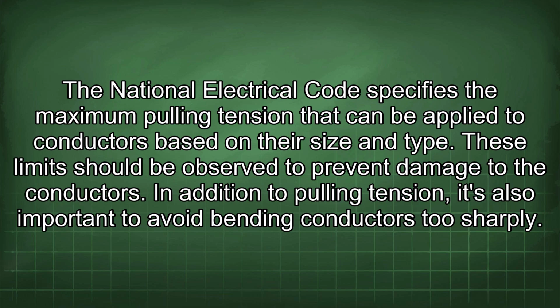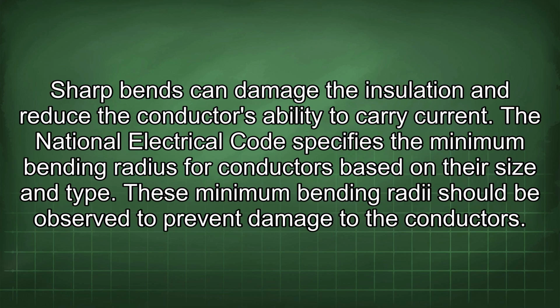In addition to pulling tension, it's also important to avoid bending conductors too sharply. Sharp bends can damage the insulation and reduce the conductor's ability to carry current. The National Electrical Code specifies the minimum bending radius for conductors based on their size and type. These minimum bending radii should be observed to prevent damage to the conductors.